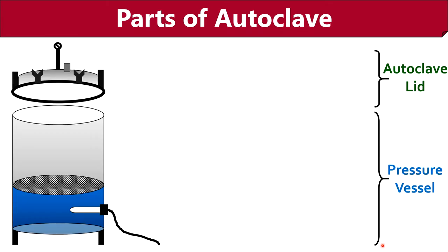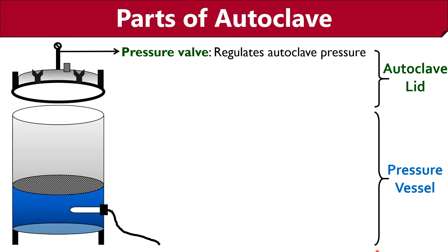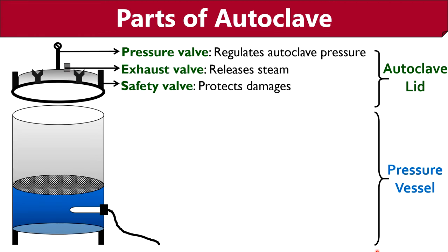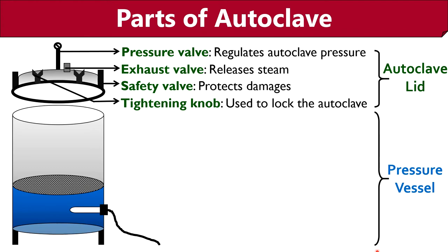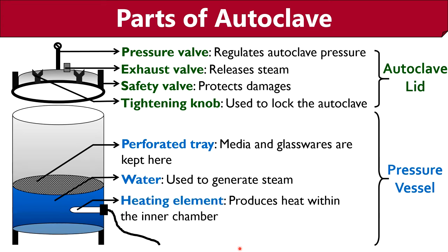Let us discuss the components of the gravity displacement autoclave and the function of each component. An autoclave lid is provided with systems like: a pressure valve that regulates the pressure of the steam jacket and inner chamber; an exhaust valve that releases steam; a safety valve that protects against damages due to overpressure; and tightening knobs used to lock the autoclave and provide a closed system. A pressure vessel contains an inner chamber and an outer jacket composed of stainless steel, and also comprises a perforated holding tray where you can keep the media and glassware. Water is added into the pressure vessel up to the level of the tripod stand, and a power cable is attached to the heating element that is necessary for steam production.